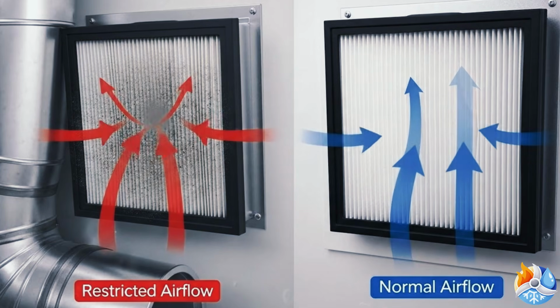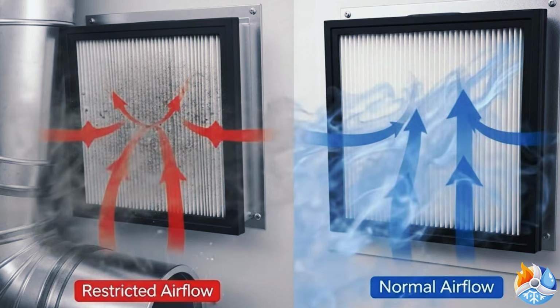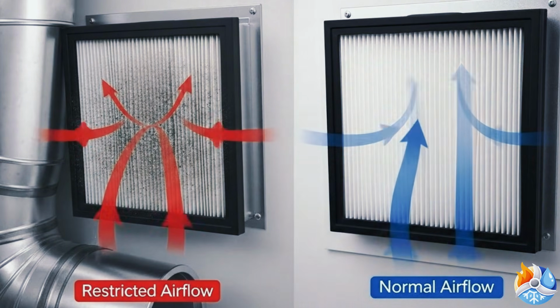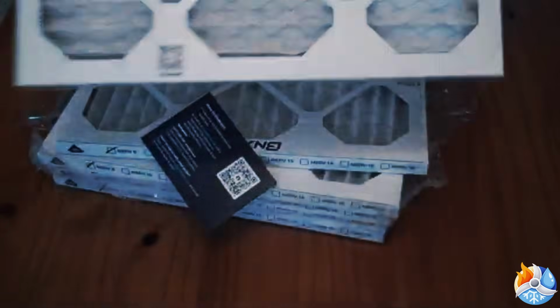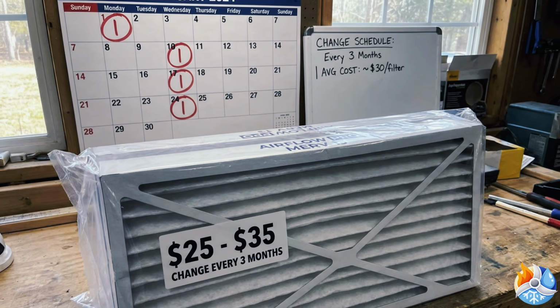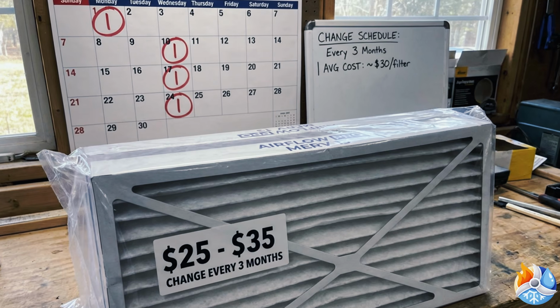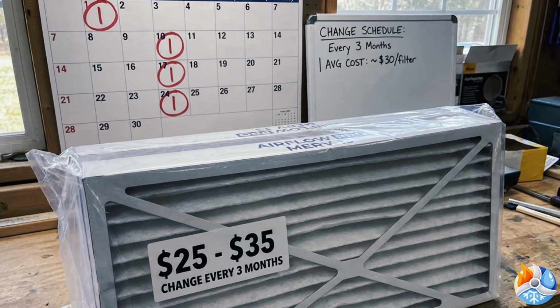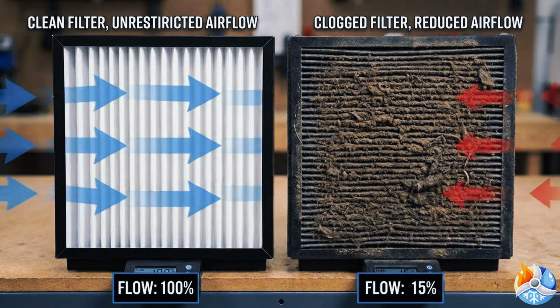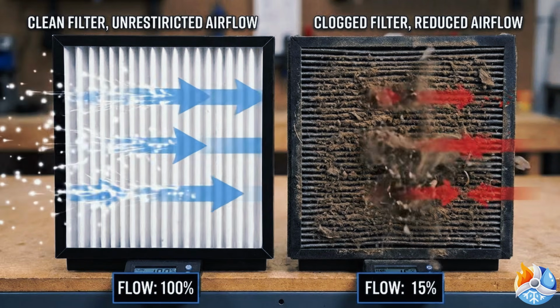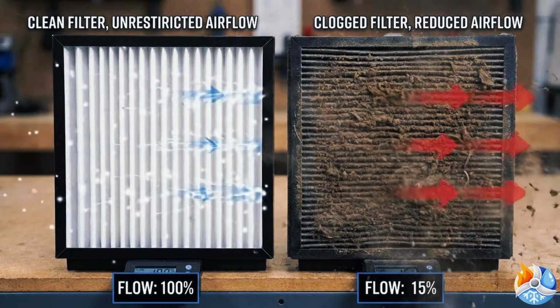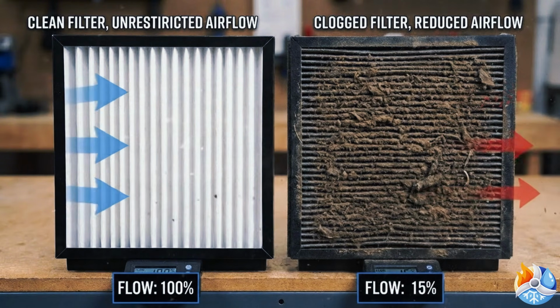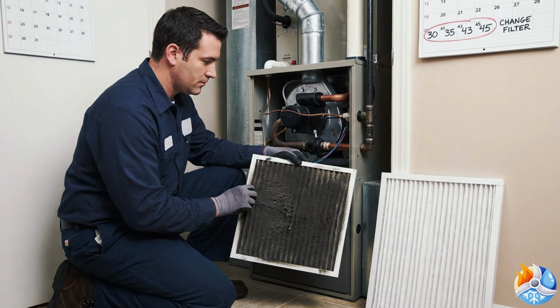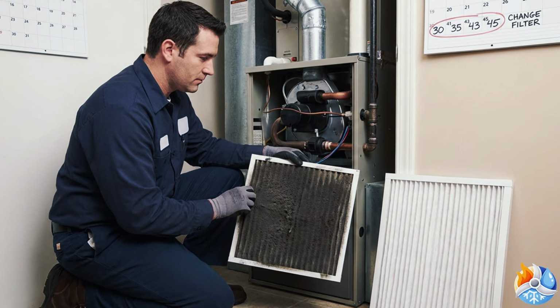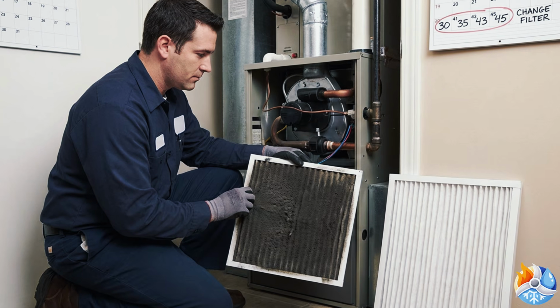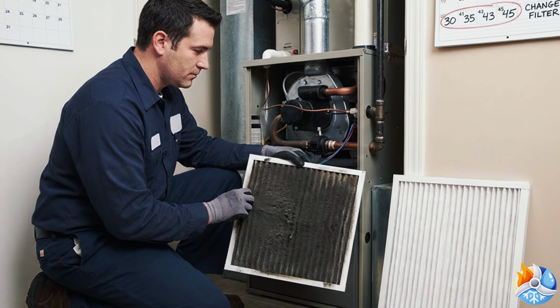And a high-rated 1-inch filter in a system not designed for it is one of the most common causes. Let us run through the numbers quickly because this part surprises people. A premium filter, $25 to $35. Manufacturer says change it every 3 months, but here is what they leave out. A top-rated filter catches far more material than a basic pleated one, which means it clogs faster. Many heating and cooling professionals recommend changing them every 30 to 45 days in real-world conditions, not 90.